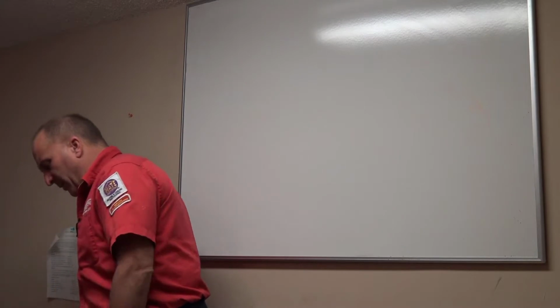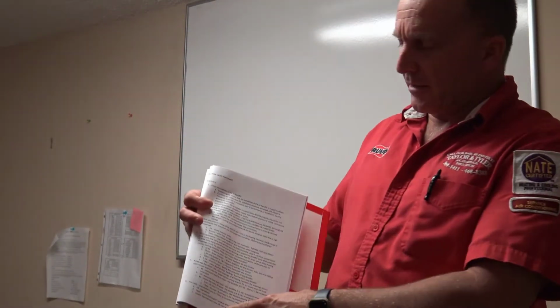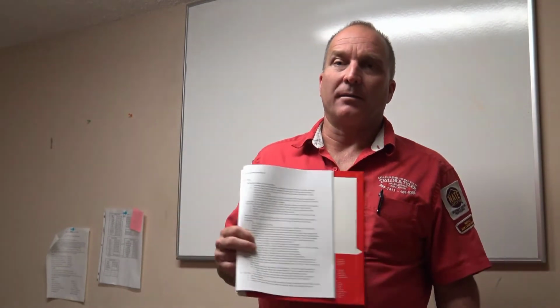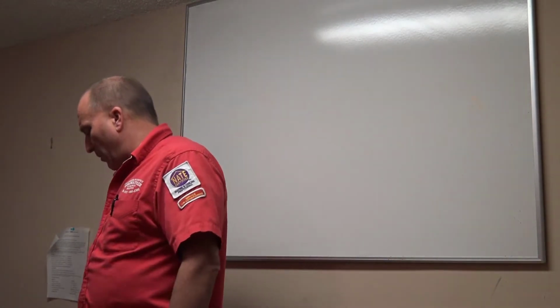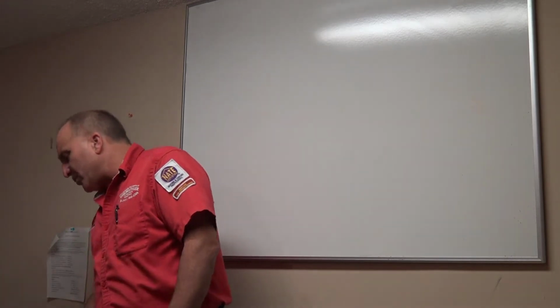And again, on this checklist, a lot of it is going to be okay, fair, poor. And I'm telling you, on this sheet right here, which is my fall PMA sheet for electric heat systems, I'm telling you what I'm asking you to go look for when you go do a fall PMA. I'm not just throwing you out in the field and saying, hey, go check that electric heat system, and you go turn it on. Okay, it runs. You didn't do a fall check then, if you just turned it on, okay? So the first deal on it is electric heat is check the condition of the air handler. What am I asking you to do? What is the condition of that air handler?